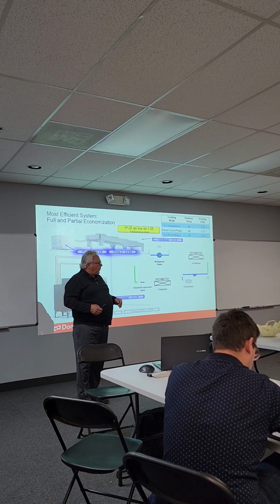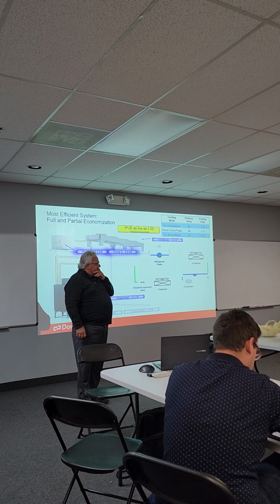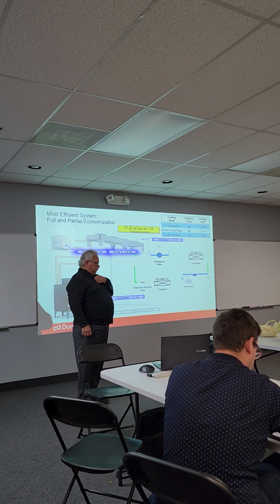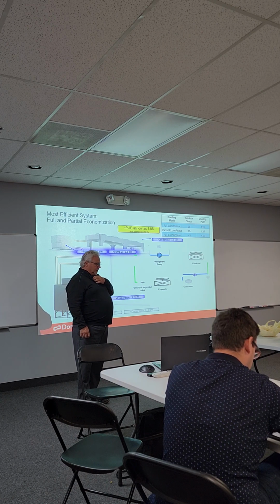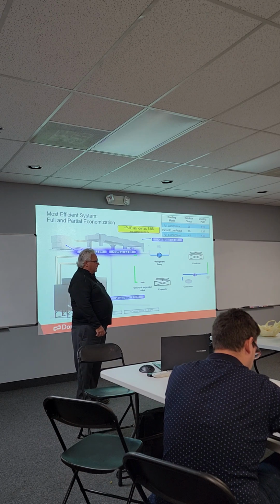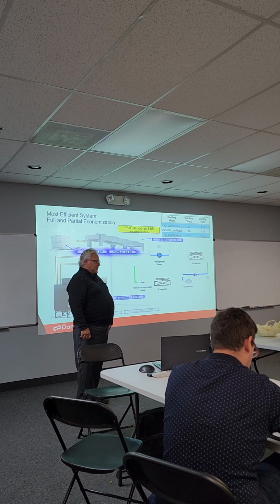I got a question for you. Your pump that you're using to move Freon, you've got to have a seal on that pump to move it. Does that seal ever leak? We haven't had problems like that. We've had more problems with glycol pumps leaking. How many times do you go to a glycol unit and they're always seeping, weeping? Because somebody started them dry, or let the glycol level get too low, or whatever the case may be.